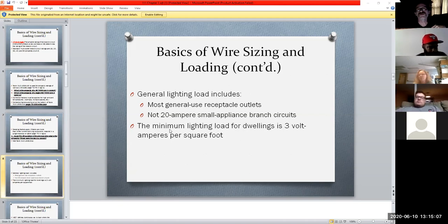So, general rule of thumb, the minimum lighting load for dwellings is 3 volt-amps per square foot. And that's a rule. So if you look at your house and you say, okay, I've got 1,200 square feet, we'd say, 1,200 square feet, and I'm allowed 3 VA per square foot. I could multiply that out and say, well, then I can have X amount. And they consider that because you need lights in your house. So they figure we're going to have X amount of lights for this amount of square footage. And that's how I figure out how I have one circuit for lights or two or three and so on.